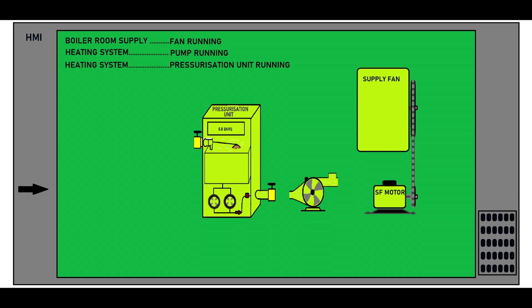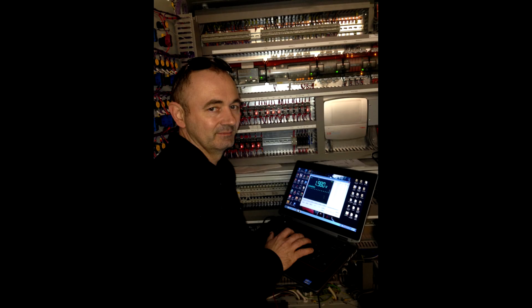And this might not be his or her fault. This is an issue related to the control philosophy. And again, you will do your own investigation. You will check the reason why the pressurization unit tripped the circuit breaker. Could be a malfunction. It's got pumps, it's got printed circuit boards, all kinds of sensors, the wiring. They could be any electrical fault. But it's not only this.